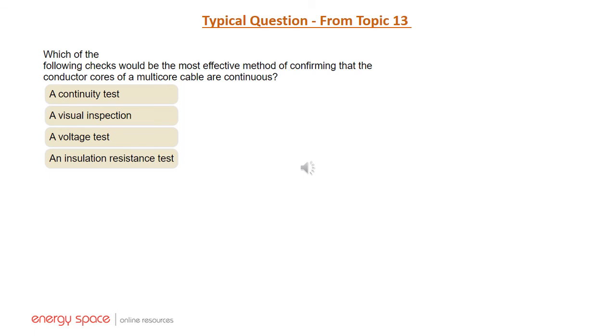Once again, not wanting to give you the answer, but the question reads: which of the following checks would be the most effective method to confirm that the conductor cores of a multi-core cable are continuous? Say we have a telephone cable which might be 50 meters long. What meter would you use just to confirm that the white wire in the telephone cable is connected to the white wire at one end and the white wire at the other end?